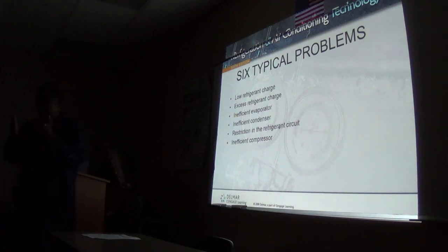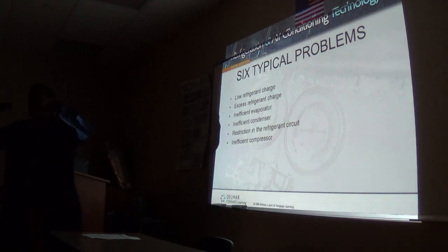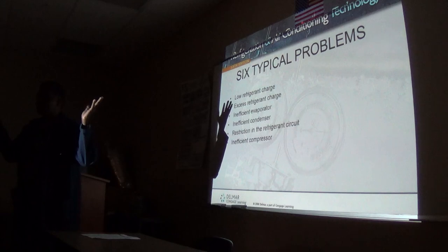You'll find eventually that the pressures will begin to change. You'll see head pressure begin to go down and suction pressure begin to go up, and there comes a point sometimes when the compressor is running but the two pressures are the same. It's not doing anything. It's just recycling, just running there in place.